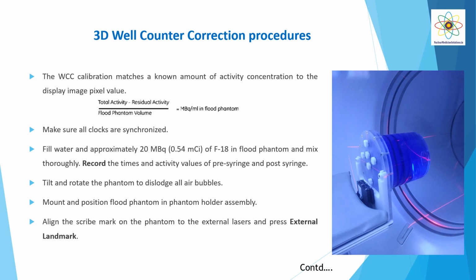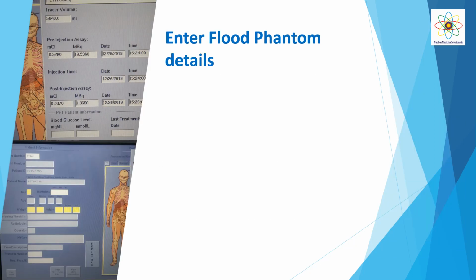Mount and position flood phantom in flood phantom assembly. Align the scribe mark on the phantom to the external lasers and press external landmark. The phantom should be centered in the longitudinal direction.